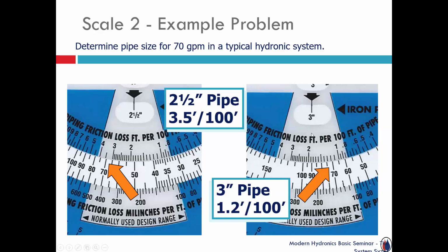So sometimes, and a lot of the charts or software that you guys are referencing will account for this, upfront cost: that 2.5-inch pipe and fittings, probably less money from the distributor, from the wholesaler, installed. The 3-inch is going to be a little bit more. How much energy is being consumed per year? Times 10 years, times 20 years, life of the system. So operating costs and all of that comes into play.